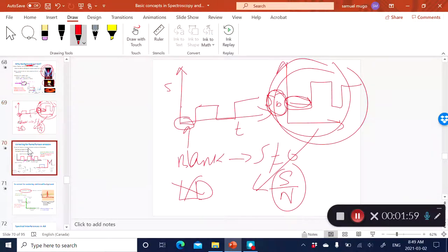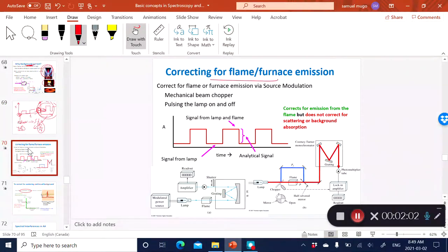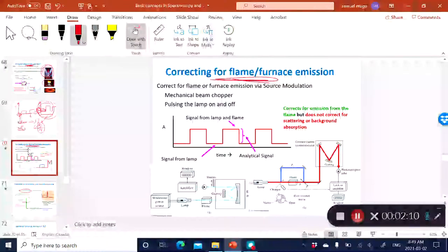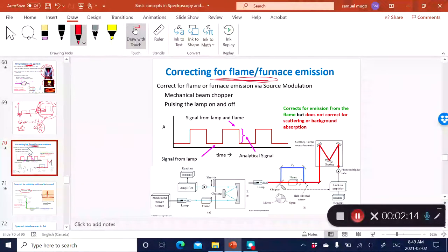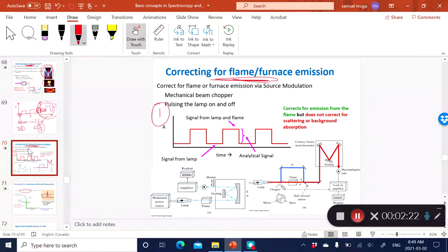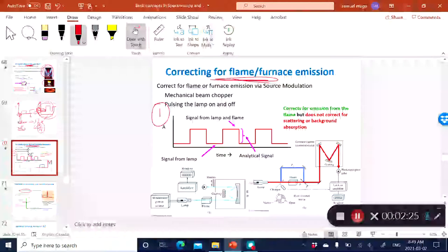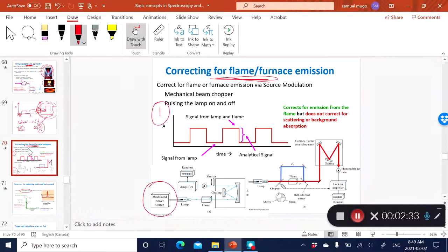We're going to discuss different ways of doing background correction in atomic spectroscopy. One very common way of correcting for background related to the flame is by simply modulating your light source. If you have a light source — and remember, in the case of AAS the most common is a hollow cathode lamp — you can modulate the lamp such that you are pulsating it, switching it on and off.